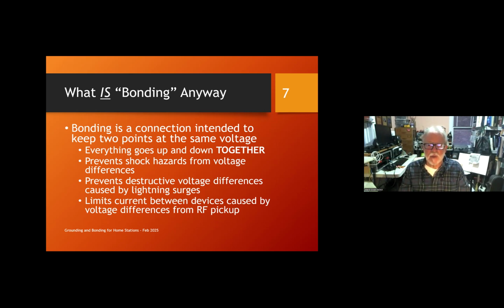And current flow is what causes shock hazards and lightning surge, destructive voltage differences, and RFI. It's current getting to where it should not be that causes the trouble. So it's like a floating dock. And I know a lot of you have experience with boats down there. You want that dock to go up and down so that when a wave comes along, it doesn't tear up the dock or break the boats away from the dock. You want everything going up and down together. And it's a very simple idea, and it works the same way electrically.